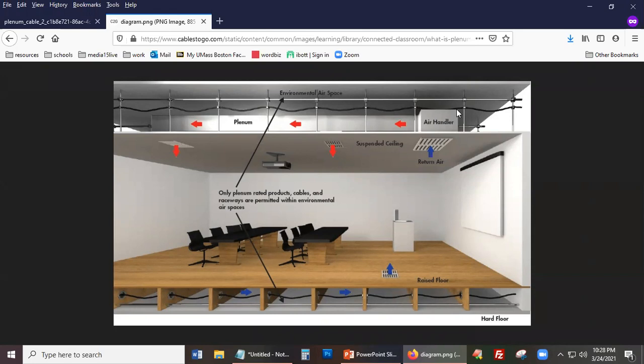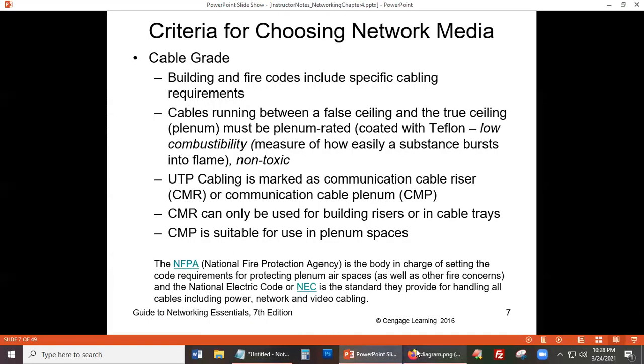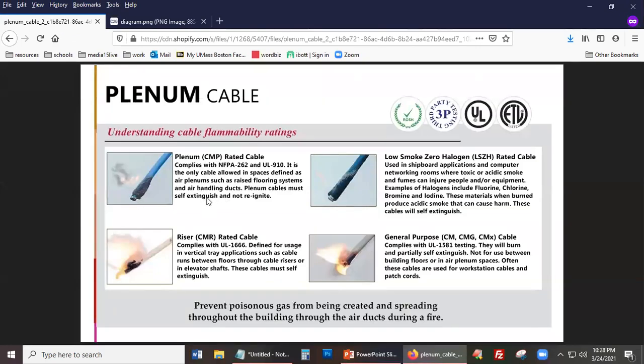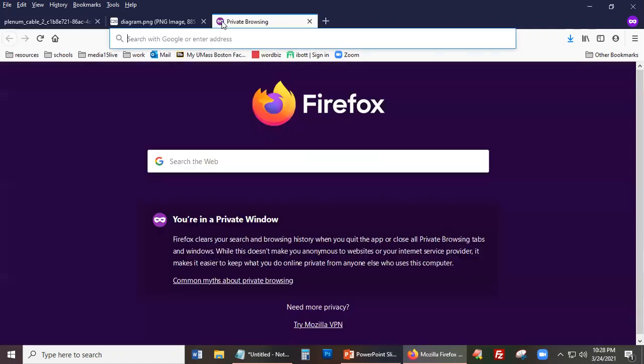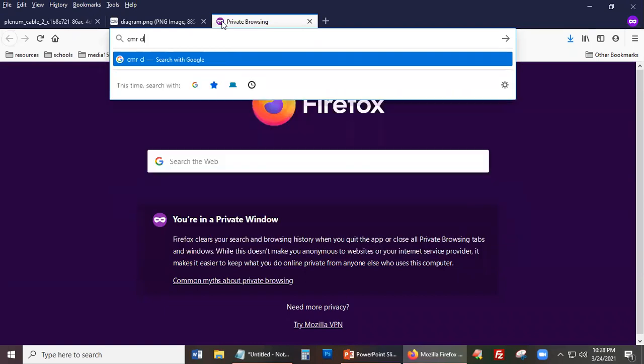To prevent the fire from getting worse, or to prevent cables from helping the fire, the cables used in plenum spaces must have a certain design. Plenum cables must be able to self-extinguish — if it self-extinguishes, it doesn't help the fire. Regular cables are defined for usage in vertical tray applications such as cable runs between floors, which would use CMR cables.